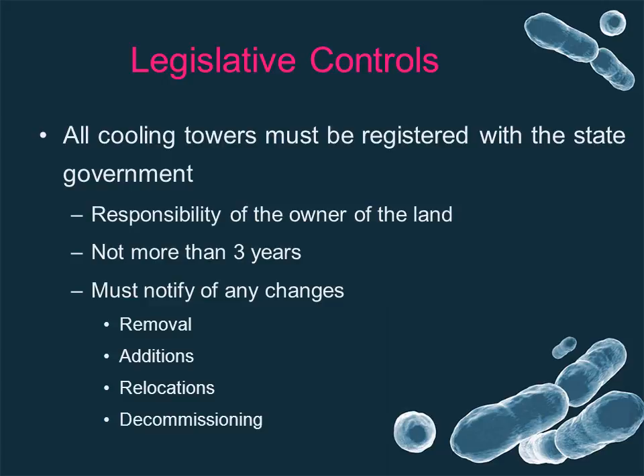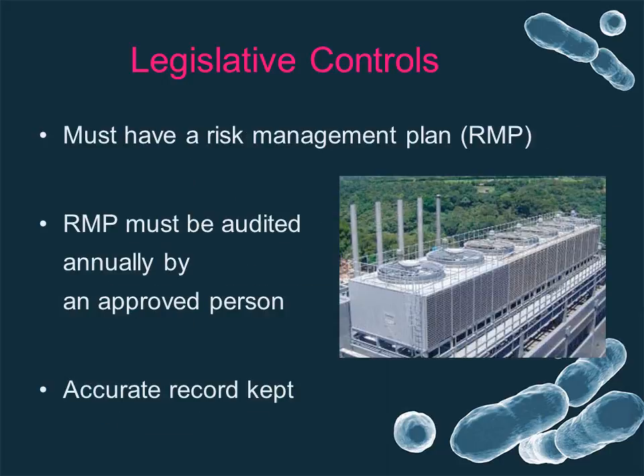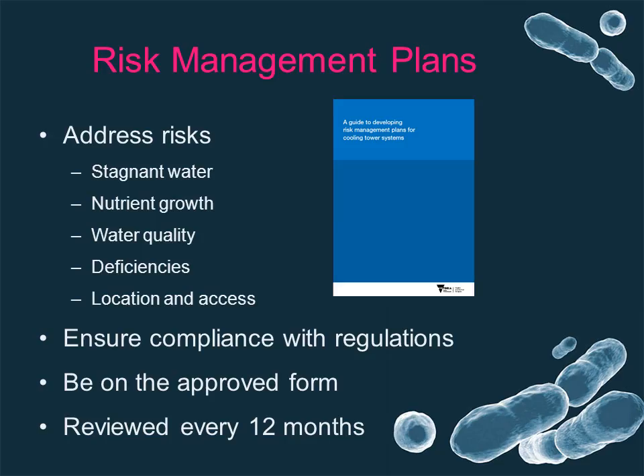As part of the Public Health and Wellbeing Act 2008, all cooling towers must be registered with the state government. This is the responsibility of the owner of the land on which the tower is situated, and towers can be registered for no more than 3 years at a time. The Act also states that cooling tower operators must have a risk management plan, and that this plan is to be audited annually by an approved person. An approved person is outlined within the Act. Owners or operators must also keep accurate records of the treatment, maintenance, and operation of cooling towers.